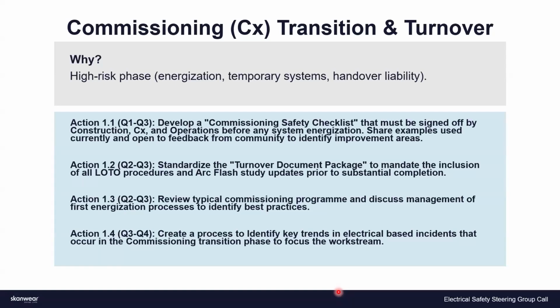You got A phase, B phase go into one thing, and the C phase is going someplace else, where you end up with ground loops or that type of thing. So having the engineers right at that time during that first commissioning, as part of taking the lockout tagout off and livening it up, has been extremely beneficial. They hate doing it, and it's extra cost, but it's been extremely beneficial.